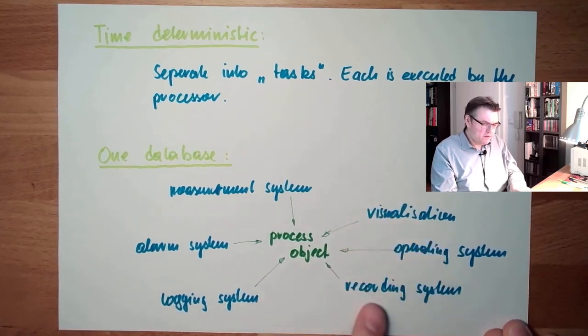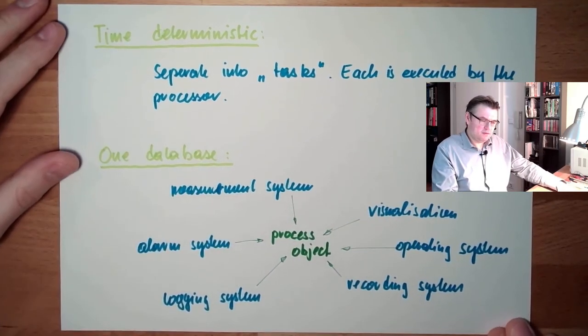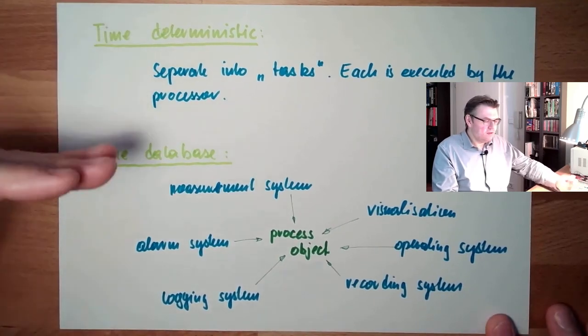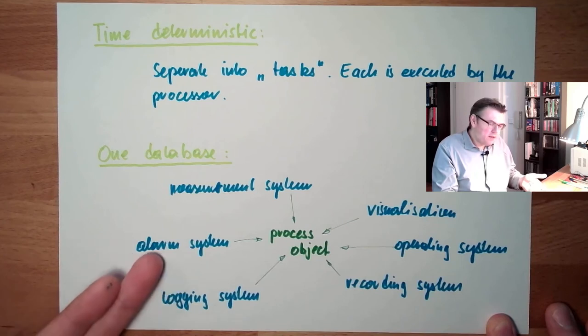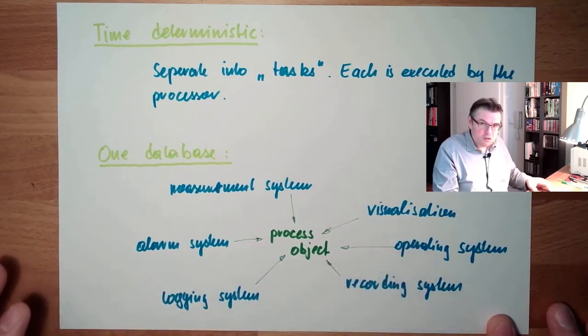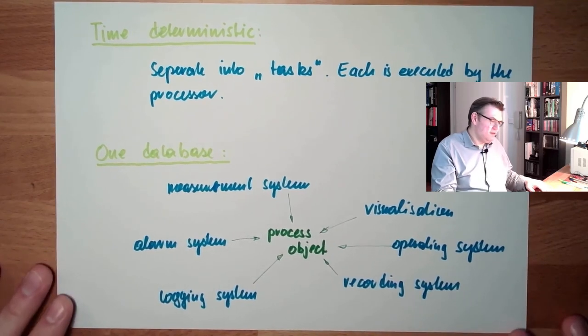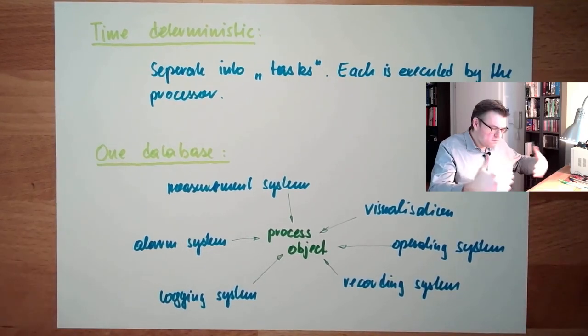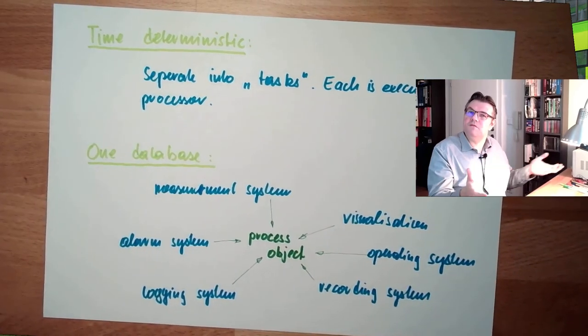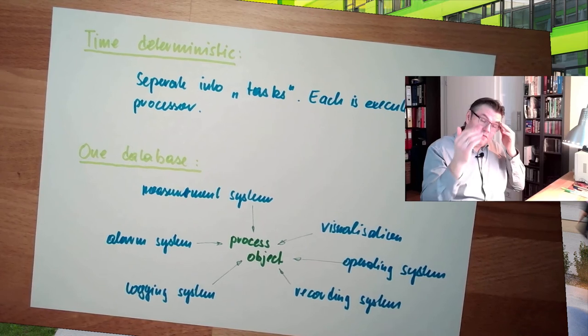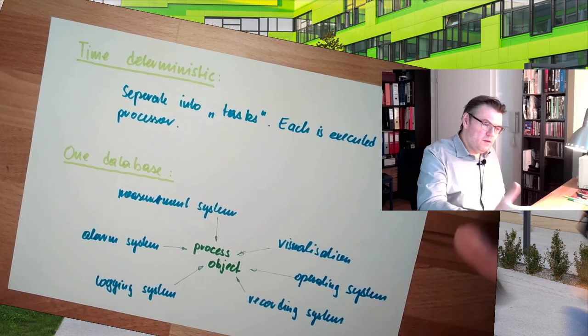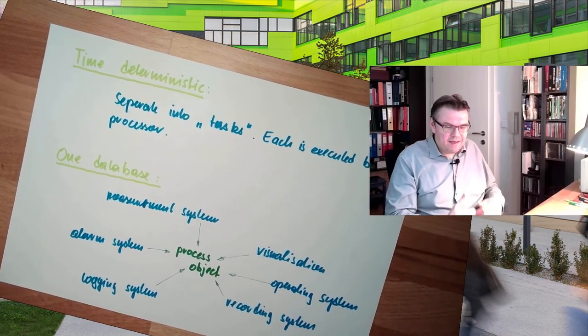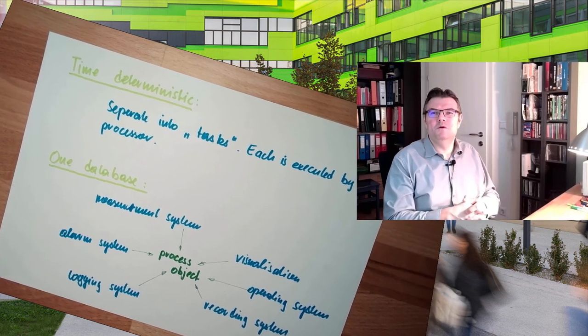Every task running there is time deterministic. These are the two things. Imagine the visualization shows a different object than the alarm system — then you get an alarm from an object you cannot see. That simply cannot be allowed. These are two things a process control system simply needs to fulfill.